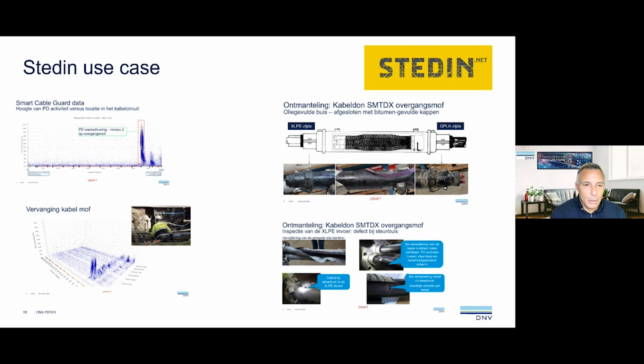This cable was going to be damaged and blow up at some point, because insulation was really minimal and a short circuit was about to happen. They were able to detect the partial discharge, replace the joint, and confirm it was the joint that was damaged and about to fail. In this way, they closed the cycle of detecting, exchanging, and then seeing that they had prevented a fault.